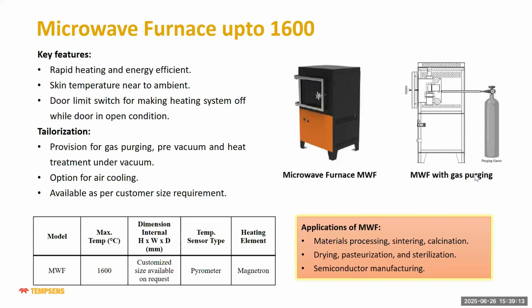We can get 1600 degrees centigrade in maybe 15 to 20 minutes for a small chamber, and the skin temperature is nearly ambient, with a door limit switch. We can also do vacuum in this type. The sensor type will be a pyrometer, and the heating element will be the magnetron. Applications of the microwave furnace include material processing, sintering, calcination, drying, sterilization, semiconductor manufacturing, and so on.